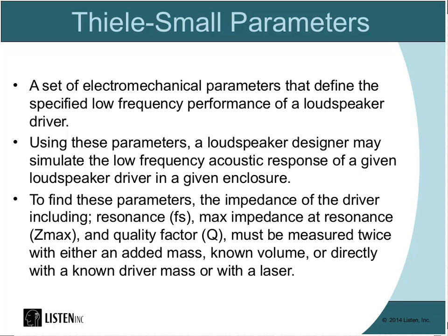In some cases, people will measure it directly with a known driver mass. They know what the cone weighs, and they're measuring the same type of speaker over and over again, or they measure it directly with a laser. But those tend to be a lot more expensive approaches, as the laser. But you can use a laser with SoundCheck and calibrate it and do it that way if you wish.